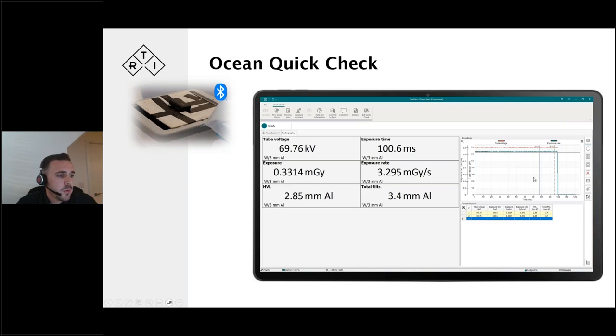We have the waveform data on the top right, and an exposure log in the bottom right. Typically we can see tube voltage, exposure time, dose and dose rate, HVL and total filtration as our typical parameters for radiography for a single exposure.